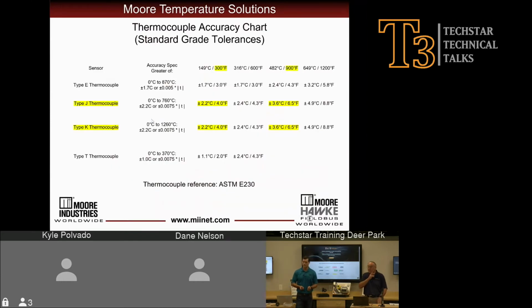So discussing tolerances a little bit more and selecting sensors a little bit more, I wanted to go into thermocouple uncertainty, and this is due to an alpha curve in the millivoltage reading that we're taking from a thermocouple that we're not able to fully compensate for when we're reading a temperature. So if you look at the column marked 300 degrees Fahrenheit, with a type J or type K thermocouple, which are industry standard thermocouples, we have an uncertainty of plus or minus 4 degrees at that 300 degree operating condition. At a 900 degree operating condition, those two thermocouples have a 6.5 degree Fahrenheit of uncertainty. So this is saying that essentially at 300 degrees, your thermocouple could read up to 8 degrees off and still be within its normal operating specifications.